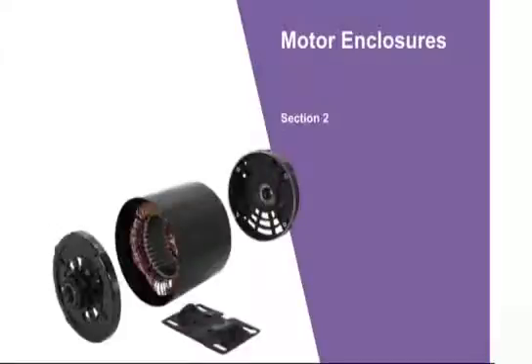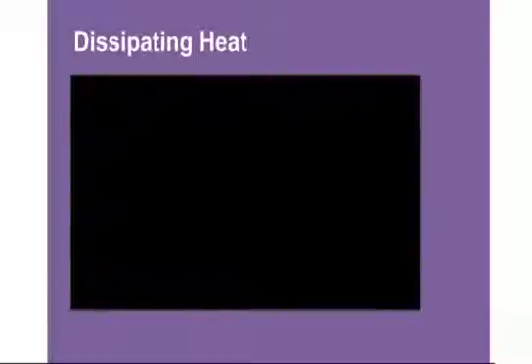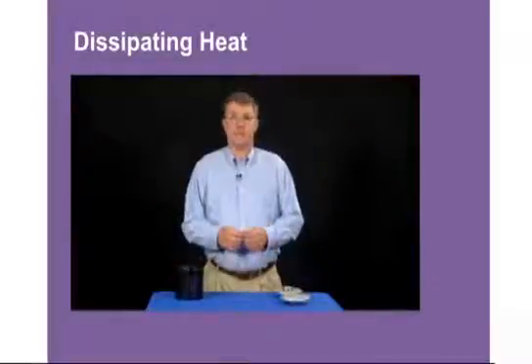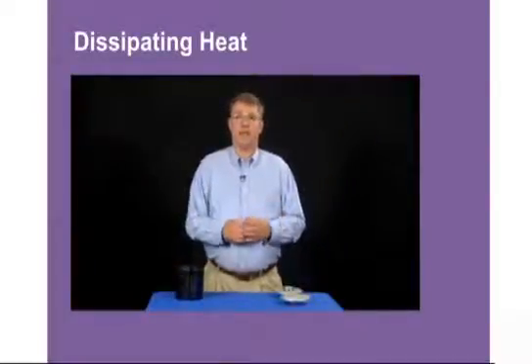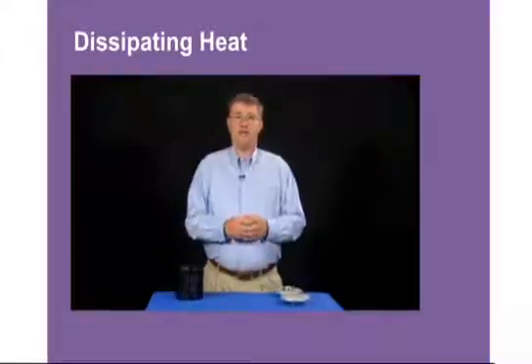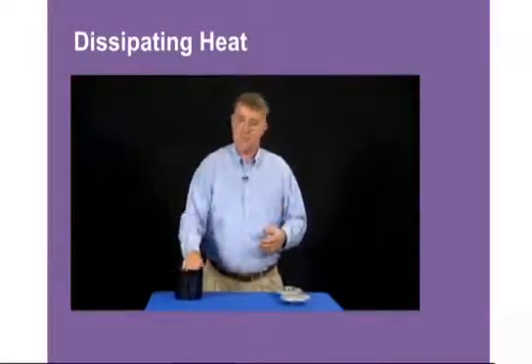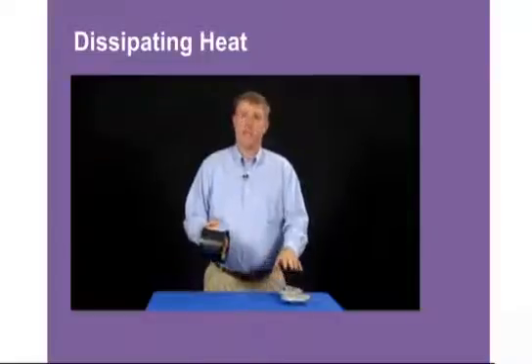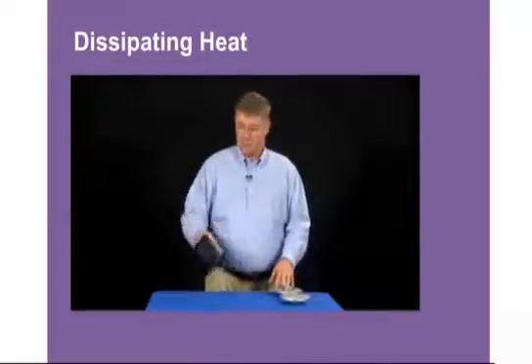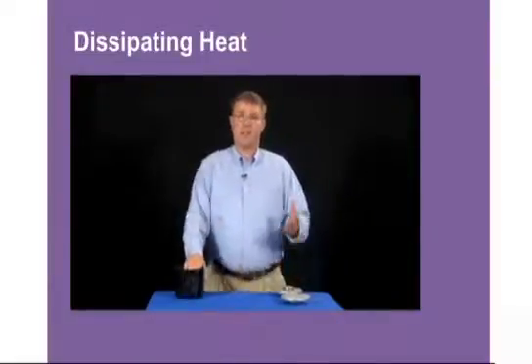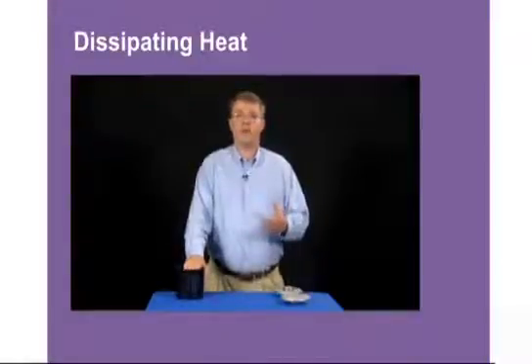This section addresses the various types of motor enclosures. The enclosure you select for an application is based on the environment where the motor is used. What ultimately kills motors is heat. Motors generate heat and the applications we put them in generate heat. We must dissipate heat from the motor using the enclosure, case construction, end bells or end brackets, taking into consideration the environment and how we can best dissipate heat.